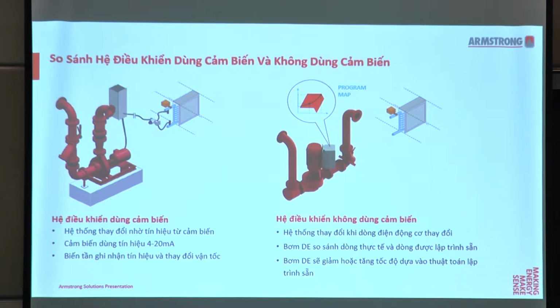Okay, so basically the changes in the system is read by, of course, the DP sensor, and this will be converted into a signal, 4 to 20 milliamp or 0 to 10 volt, and the VSD will read the signal and will modulate or regulate the speed accordingly, whether it is speed up or speed down, to ensure and maintain the pressure. Okay.